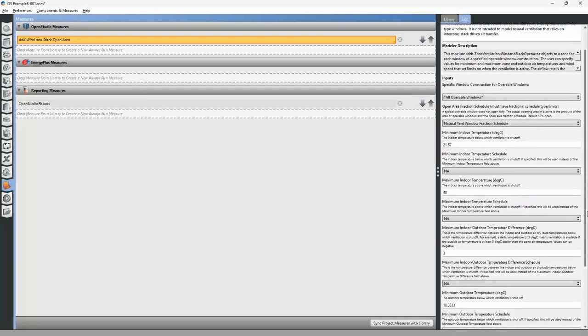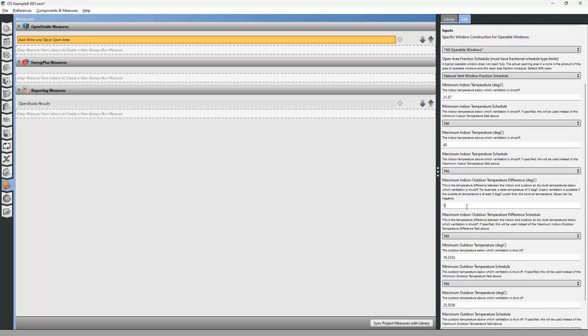The next parameter is maximum indoor-outdoor temperature difference — the temperature difference below which ventilation is shut off. Three degrees is quite small; you won't get much natural ventilation below a three-degree temperature difference, so it's pointless to open the windows if the difference is below three degrees. The stack effect driving ventilation is proportional to temperature difference — the higher the difference between indoors and outdoors, the more natural ventilation you get.